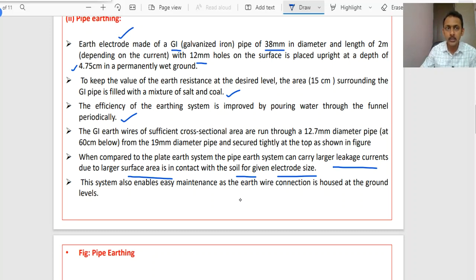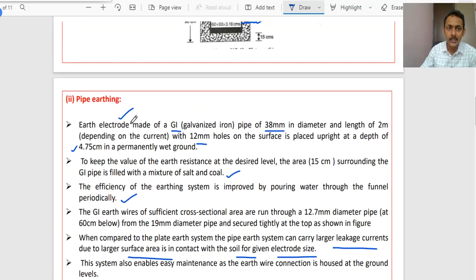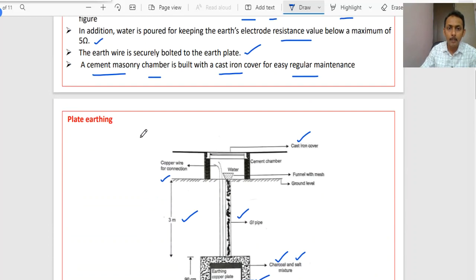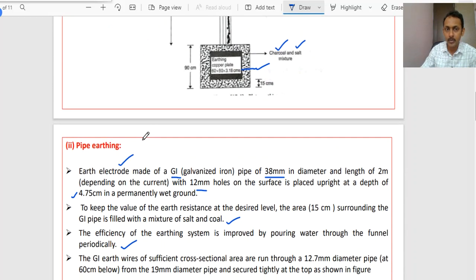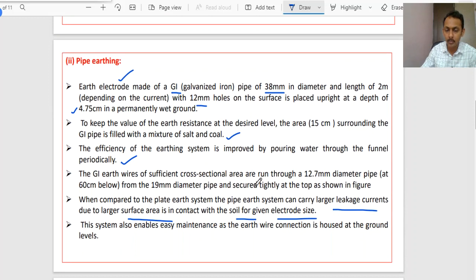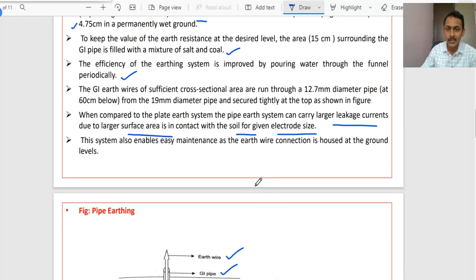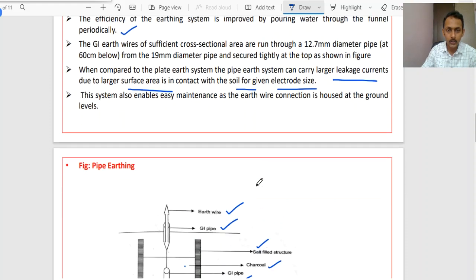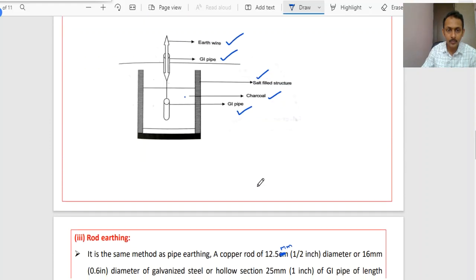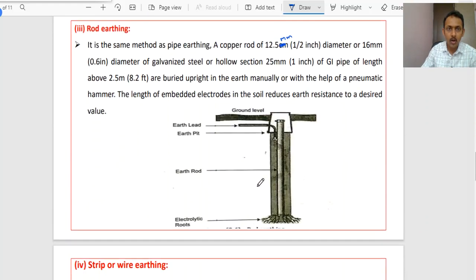So its meaning is, it is going to offer less resistance compared to the plate earthing system for the same dimensions, right, for the same given electrode size? It is going to offer less resistance. Because of that, it is going to allow more leakage current to pass through the earth wire. So this is the pipe earthing, and next one is the rod earthing.